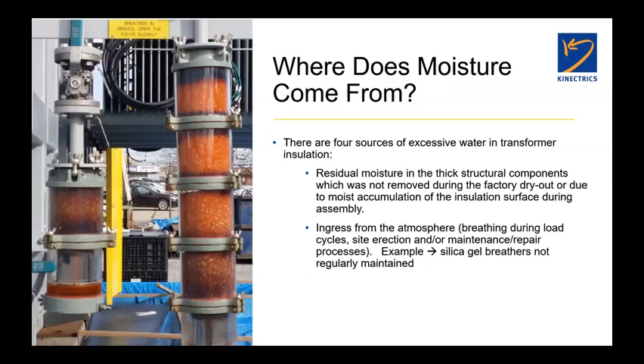But beyond that, transformers, especially really large ones, are an interesting product. When you go to buy a car, you go to the dealer, you hand them the check, and they give you the keys, and you drive away. A large transformer is built at the factory, it's tested, then they take it apart and ship it to site and rebuild it on site, and then it has to be re-dried and refilled with oil. And sometimes, more often than not, things like bushings need to be installed, radiators need to be put on. In those commissioning operations, we call that the dressing out of the transformer.